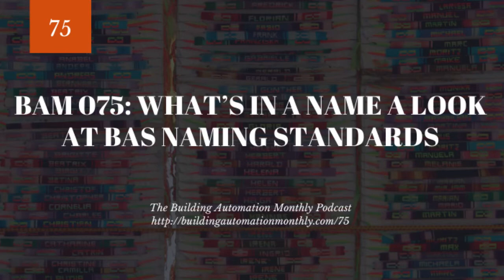The next is that it's got to be concise. Now, what if instead of Water, dash, FLR1, dash, RM 101, dash, VAV, we did Water Building dash Floor spelled all the way out, then One spelled out rather than just the number, then dash Room spelled out, then 101 spelled out, and then spelled out variable air volume box. In most modern BASs, you might actually exceed the character length you're allowed for a name, because every time you store an object in computer memory with more than a certain number of characters, that eats up a lot of memory. And if you do that too many times, you can eat up all the memory resources of the BAS.